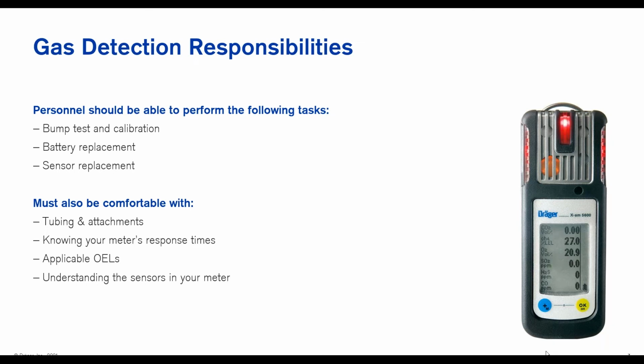And understanding the sensors in your meter. This particular meter has a carbon dioxide sensor, a methane sensor for measuring LEL, oxygen, sulfur dioxide, hydrogen sulfide, and CO. So we've got several different sensors, and understanding what they are and how they operate—we'll get into that in depth in the next webinars—is important, because one meter's methane sensor measuring LEL may work completely differently from another meter measuring the same thing but using different sensor technology. Understanding these things is going to be crucial for our gas detection personnel.